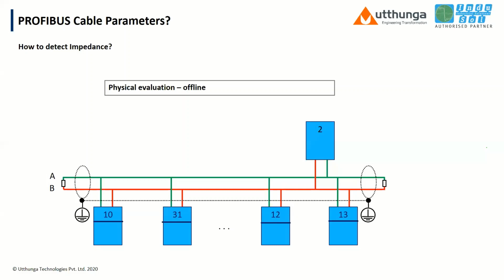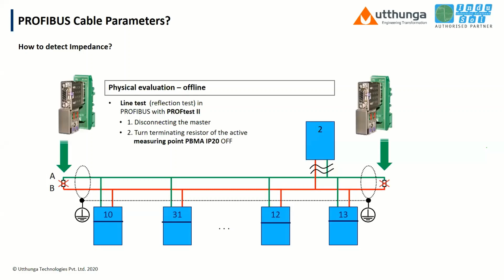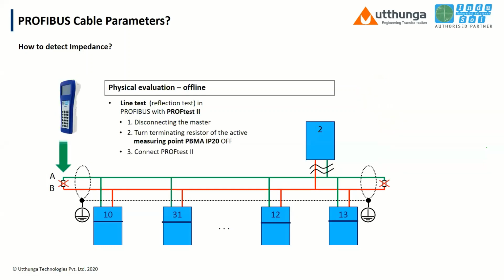And how do we use Profi test? This is just for your visualization. We need to analyze at the start of the segment and the end of the segment. Profi test is clearly an offline tool. You need to plug the cables out and test it. If you test from the start of the segment till the end of the segment, it will test whether the shielding is okay, the cable impedance is okay, or any cable break is there. These complete details you will get in one shot, but you have to test at both ends. So that is Profi test, the cable tester.